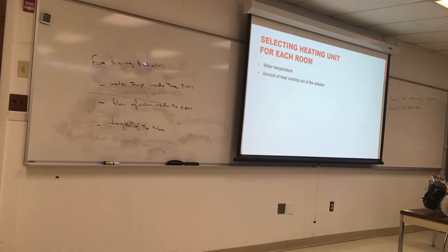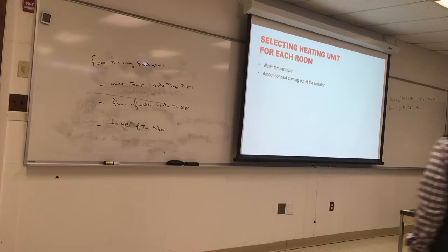Temperature drop. Do you expect the water coming in to have the same temperature coming out? No, otherwise, what's the point? So we always assume a 20 degree temperature drop. I want to drop by 20 degrees. So the water coming in is at 180, and you want it to come out at 160. You can do that. So we want to lose 20 degrees of water temperature inside the tube.